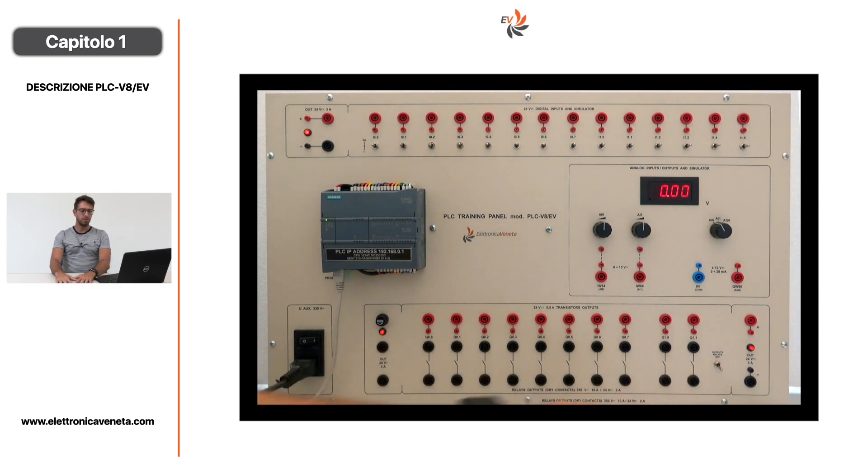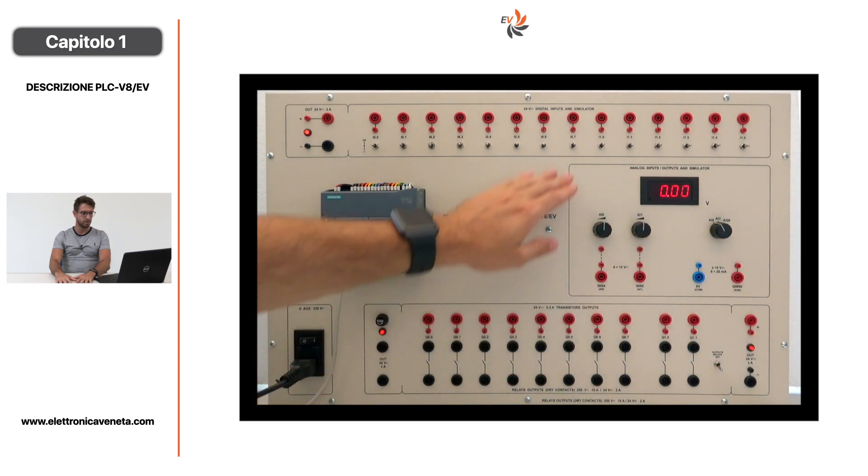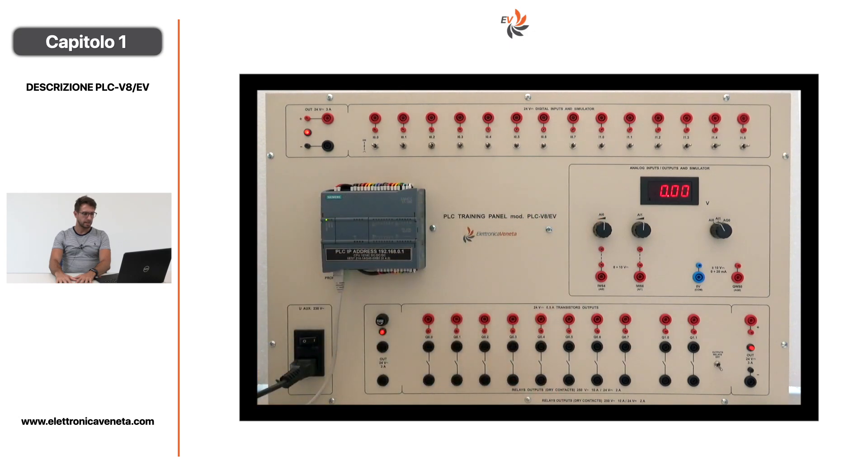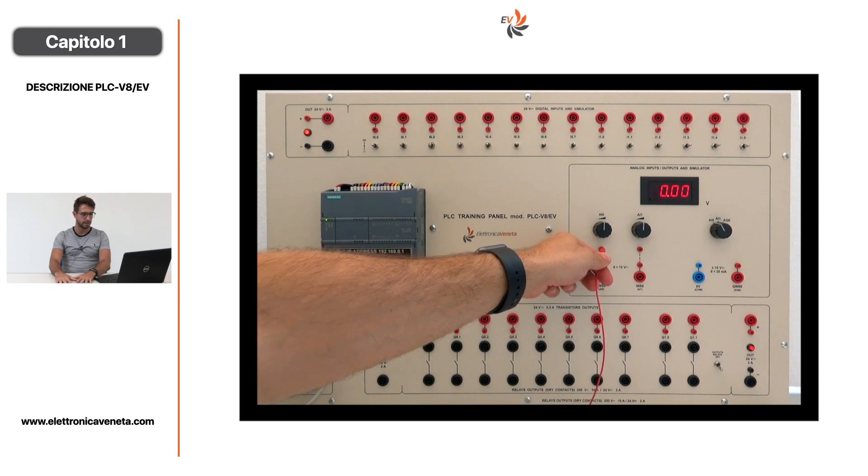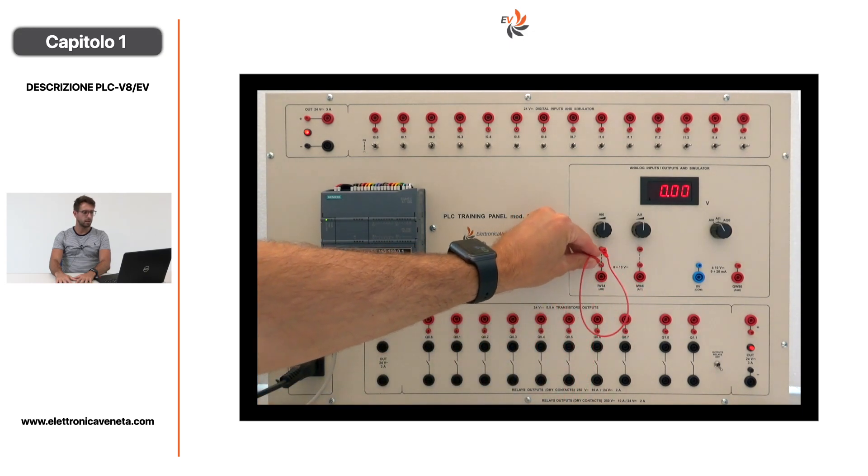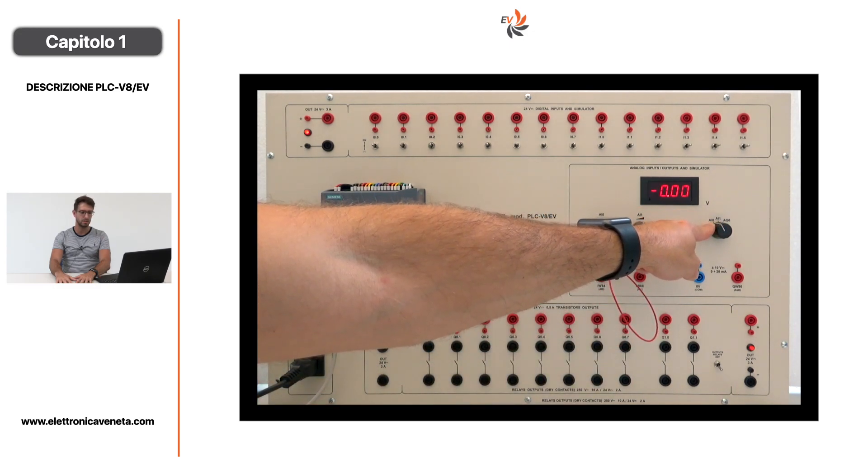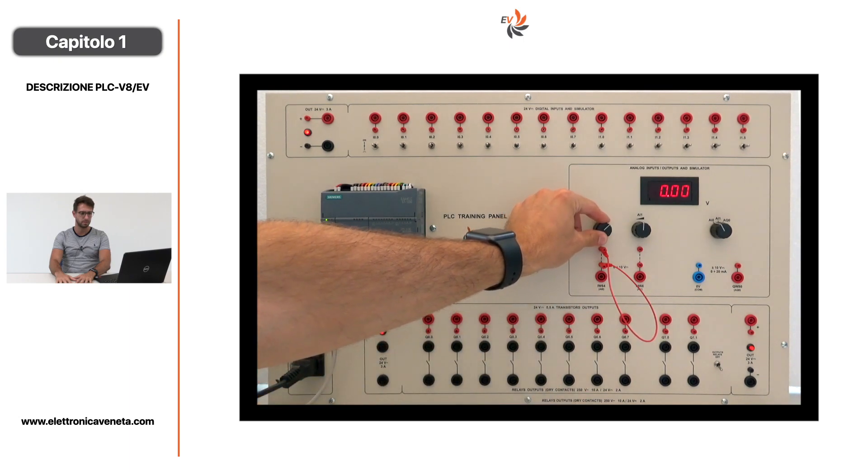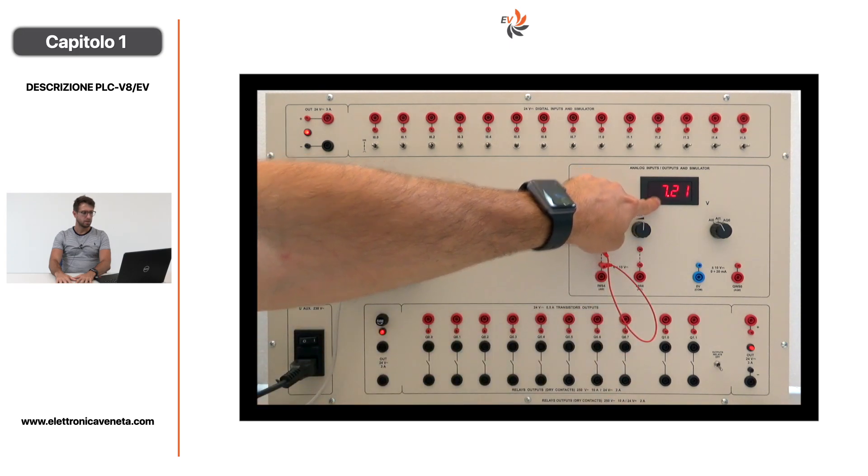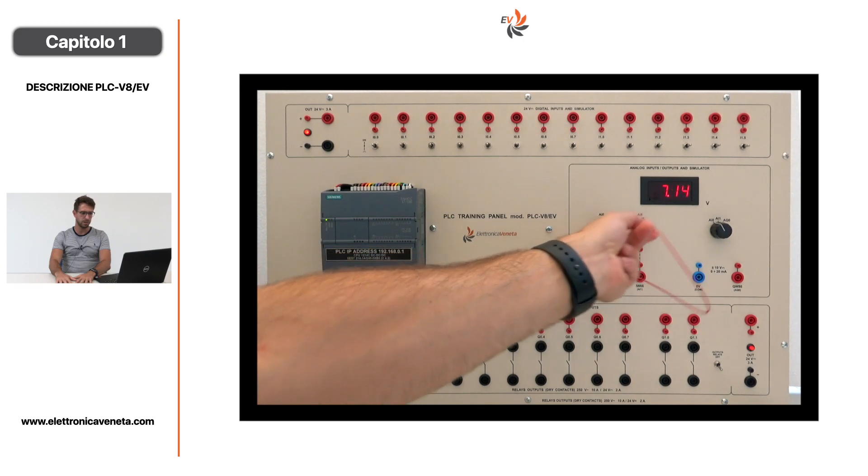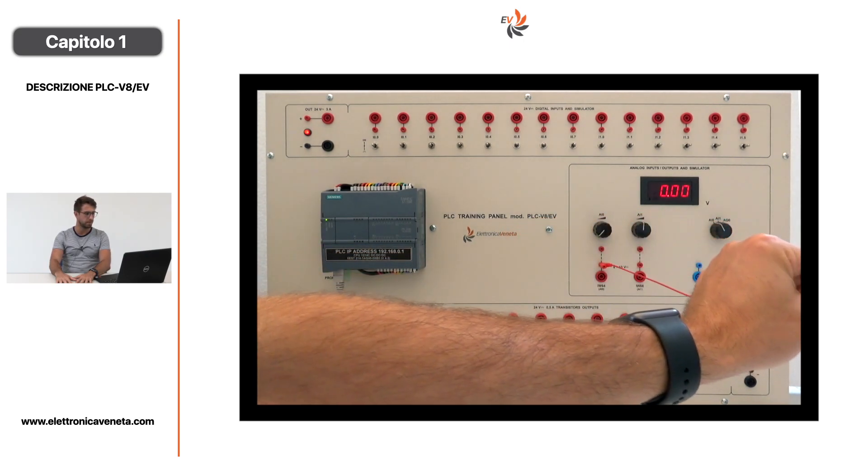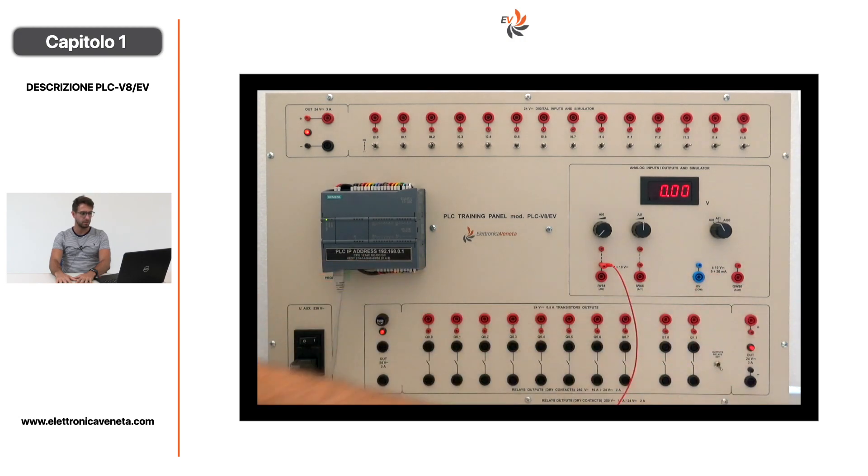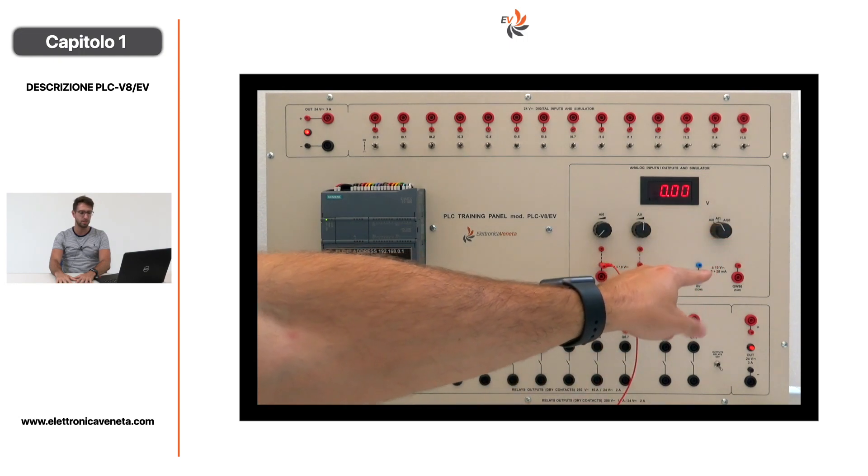Per quanto riguarda le risorse analogiche, abbiamo i potenziometri 0-10V per la simulazione dell'ingresso analogico. Collegate le due bocole da 2 mm una sopra l'altra, si seleziona l'ingresso al display e ruotando il potenziometro si visualizza la tensione imposta. Collegando il ponte si può inserire un segnale esterno, sempre 0-10V o 4-20mA. L'uscita analogica è sempre più o meno 10V, 0-10V, 0-20mA, ed è visualizzabile settando la terza posizione del selettore.